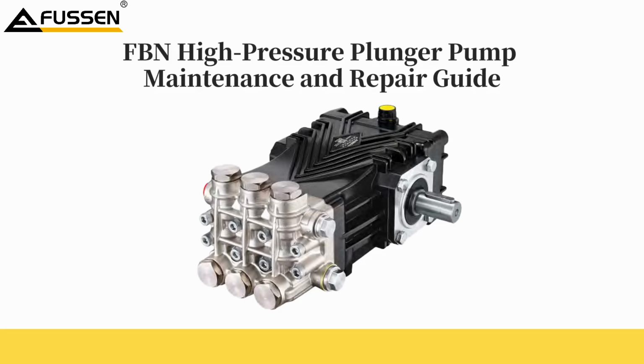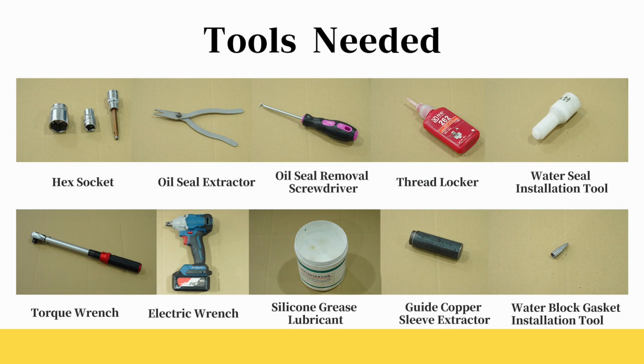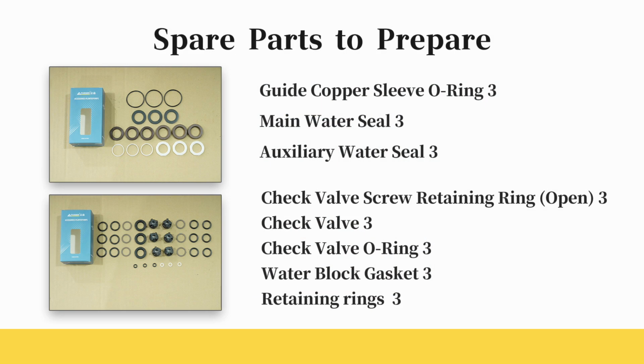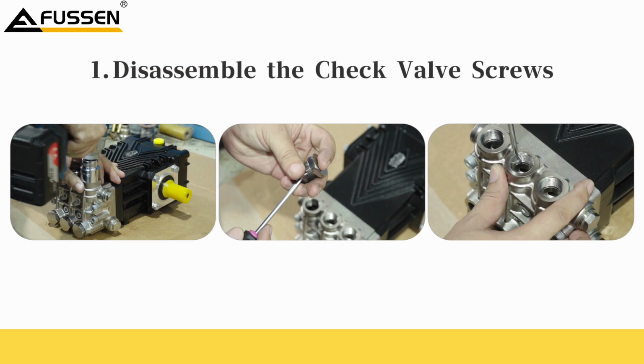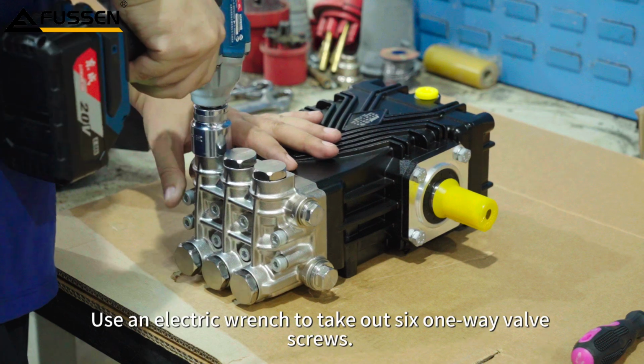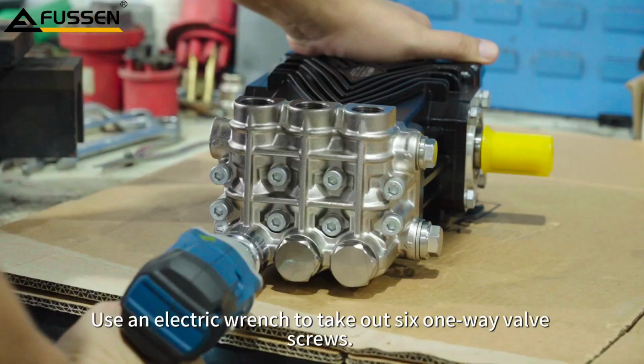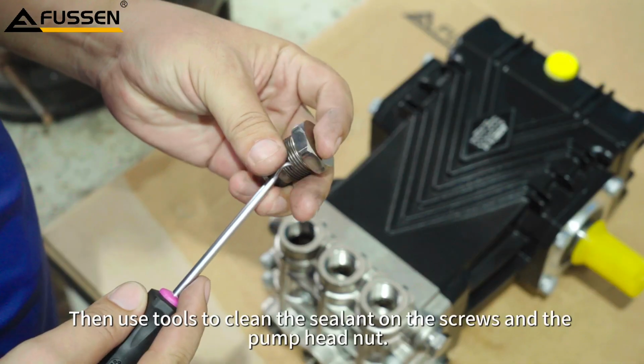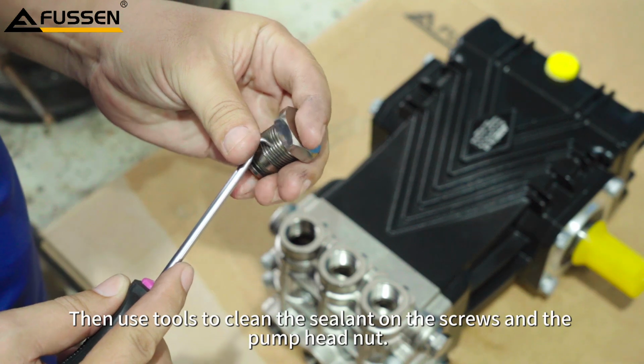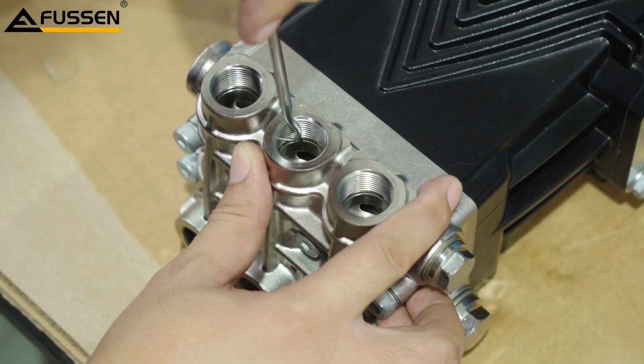FBN High Pressure Plunger Pump, Maintenance and Repair Guide. Tools needed. Spare parts to prepare. Disassemble the check valve screws. Use an electric wrench to take out 6 one-way valve screws. Then use tools to clean the sealant on the screws and the pump head nuts.